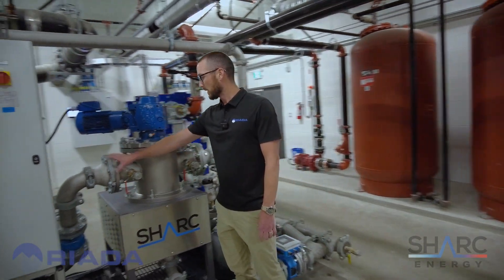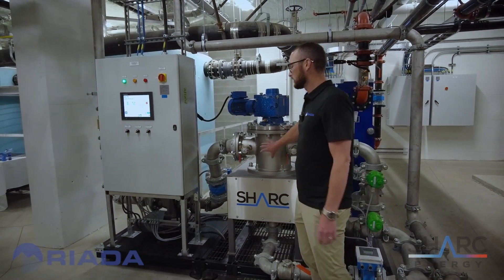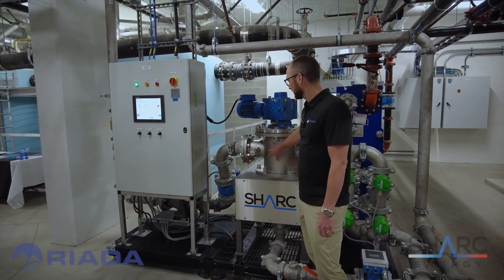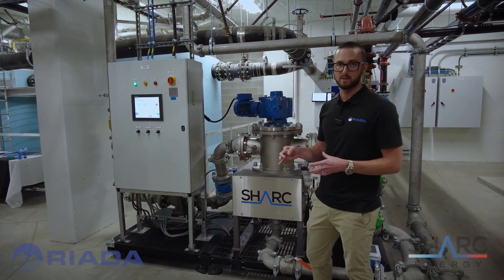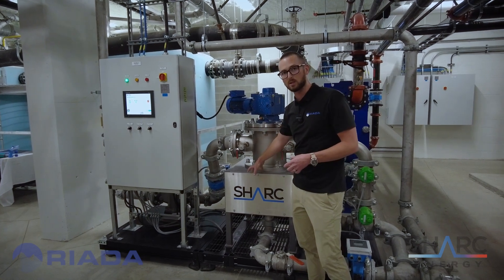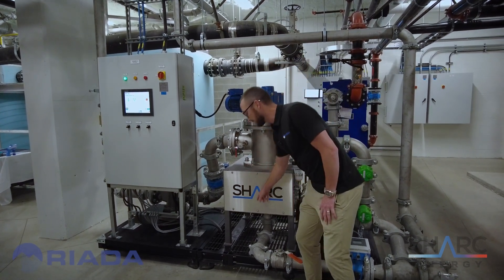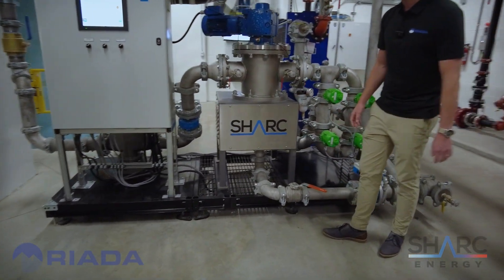As we move through the skid, that macerated wastewater comes here to the mains — this is the heart of the SHARC, the SHARC module. There's a filter basket in here that filters the wastewater to a maximum solid of three millimeters. This motor controls an auger that separates any solids larger than that and sends them down to a bypass line, temporarily bypassing the larger solids.